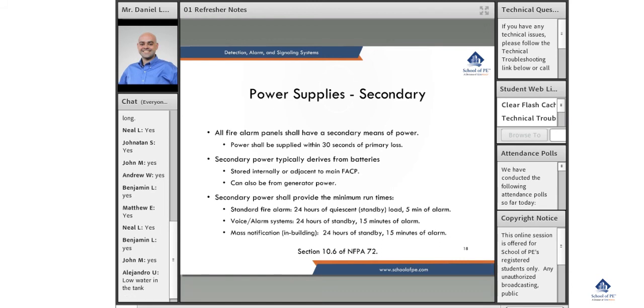How large do you need to size these things? Code has three different requirements. The standard fire alarm system has to have 24 hours of standby load and five minutes of alarm. It's not one or the other - the system upon loss of power must be able to operate standby for 24 hours and then operate the alarm system for five minutes.